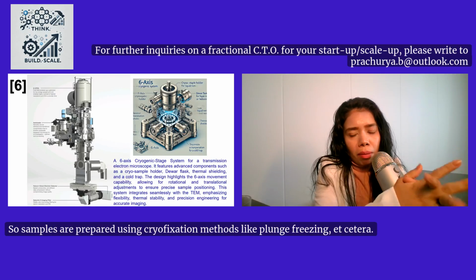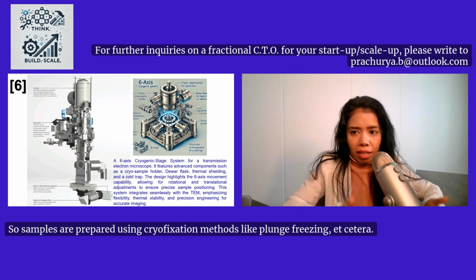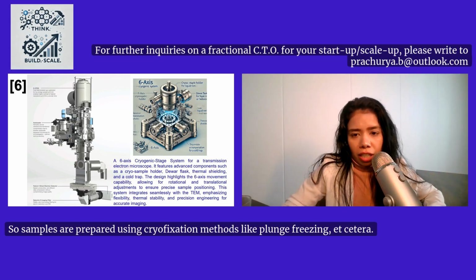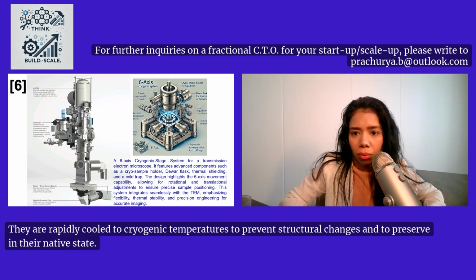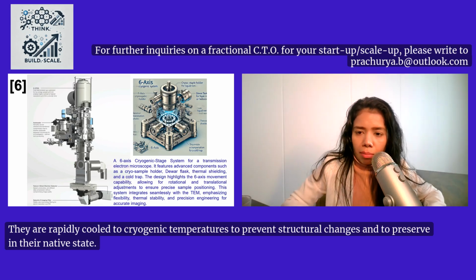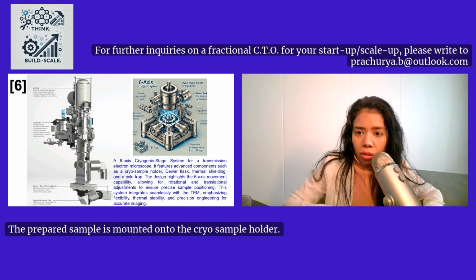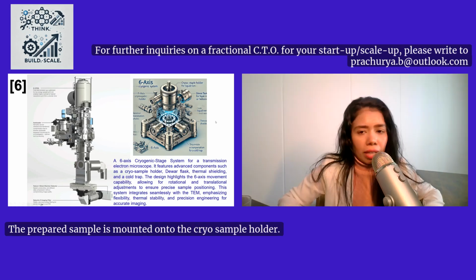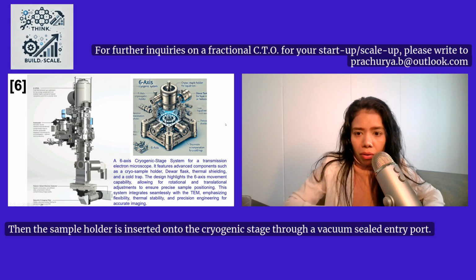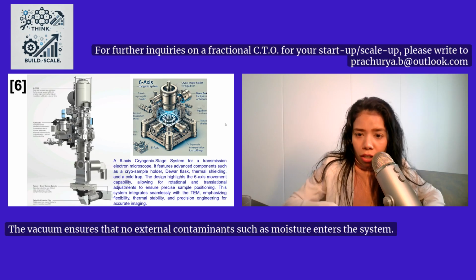Samples are prepared using cryofixation methods like plunge freezing, etc. They are rapidly cooled to cryogenic temperatures to prevent structural changes and to preserve them in their native state. The prepared sample is mounted onto the cryo sample holder, right here. Then the sample holder is inserted onto the cryogenic stage through a vacuum sealed entry port. The vacuum ensures that no external contaminants such as moisture enter the system.